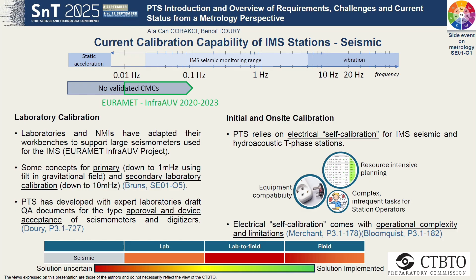PTS, together with the expert laboratories, has developed draft quality assurance documents for the type approval and device acceptance of seismometers and digitizers. And for initial and on-site calibration, PTS relies on electrical self-calibration for seismic and hydroacoustic T-phase stations, which presents some operational complexity and limitation.